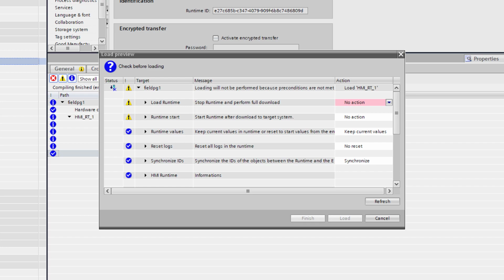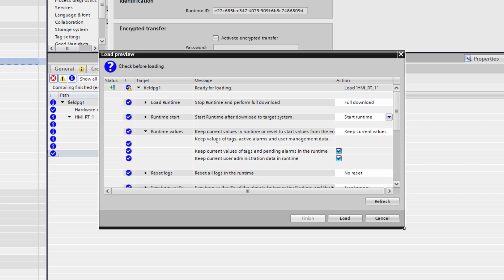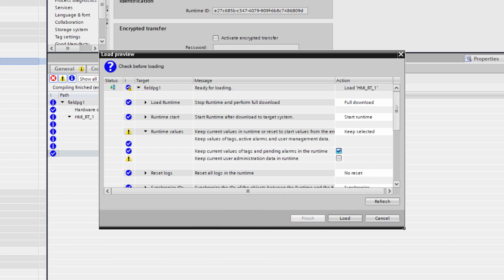Here we'll want to change the runtime values because we want to overwrite the user administration. We'll start out by doing a full download, and then we'll start the runtime upon launch. Last but not least, on the first download, the suggestion is to make sure that we uncheck Keep Current User Administration Data in Runtime. That way we can download the new user administration. Last but not least, we'll just go ahead and load.